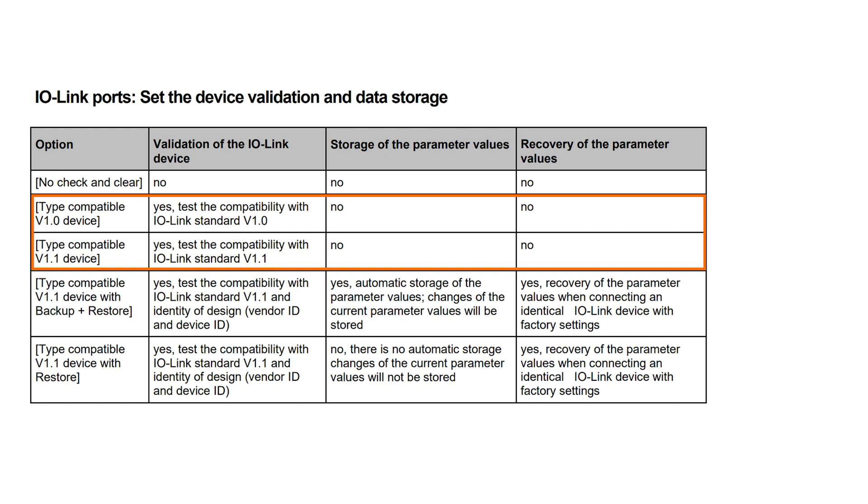The next two options, Type Compatible Device, can be used to check that the correct sensor is connected. This can be done with the new 1.1 standard and even with the first IO-Link Standard 1.0. Only the device type is checked, without any kind of data storage.